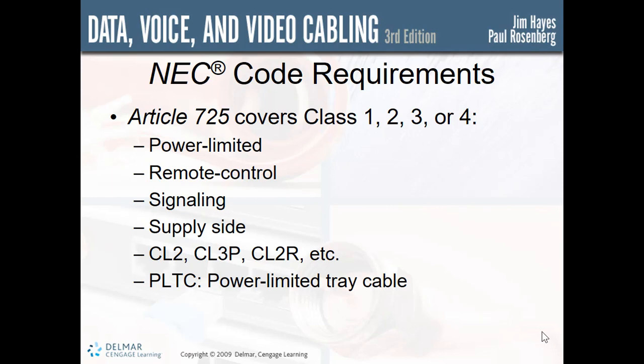Class 3 circuits are similar to Class 2. They are inherently limited in capacity. They may require no overcurrent protection or may have their capacity regulated by some combination. Class 4 circuits are Class 1 circuits that are also isolated, and they are used only for process control instrumentation.